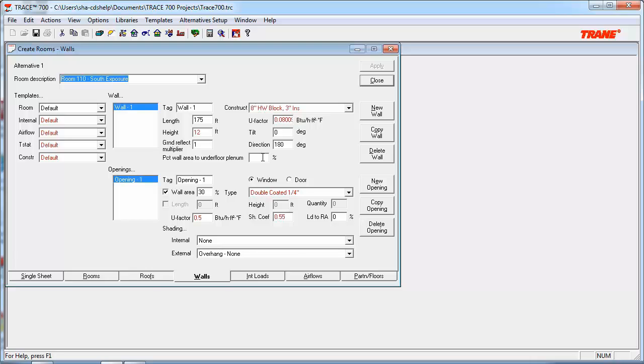So you'd end up creating two walls, one with 0% wall area to the underfloor plenum, and one with 100% wall to the underfloor plenum. As a special note, Trace assumes that all of the wall area assigned to the underfloor plenum is opaque, and that the underfloor plenum is sealed from outdoor air infiltration.